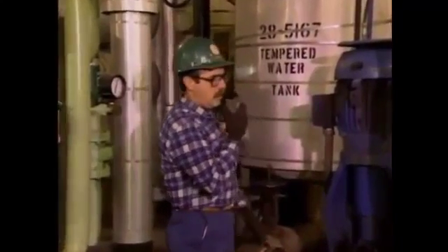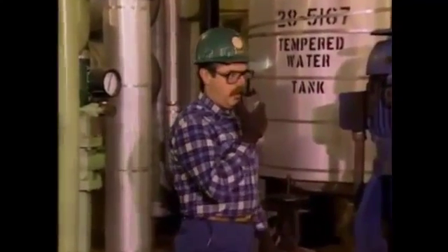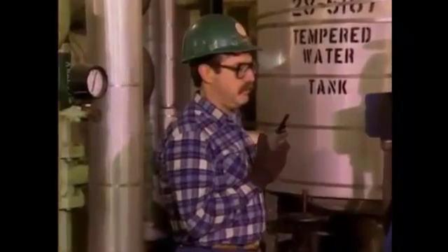As the tubes become blocked or fouled, the differential pressure will increase above the normal value. Once again, the cause of the problem should be investigated and supervisory personnel should be informed.